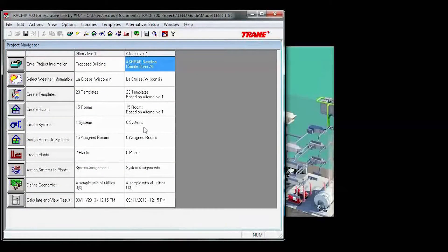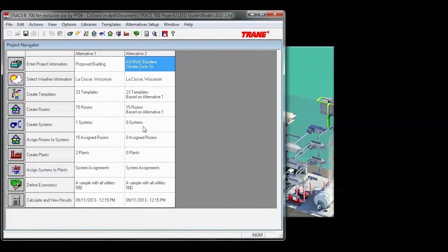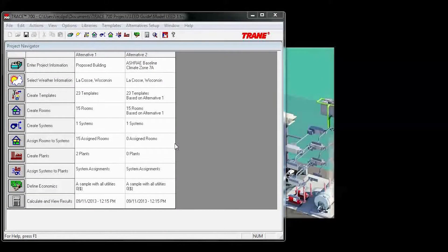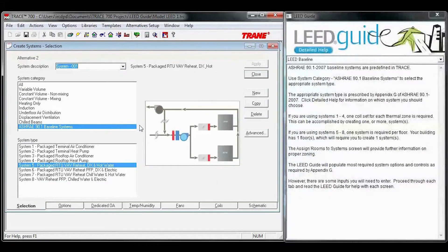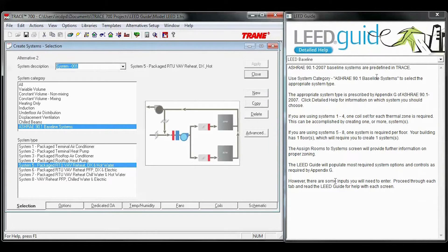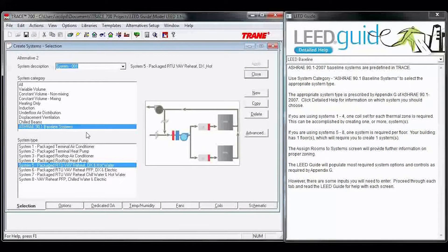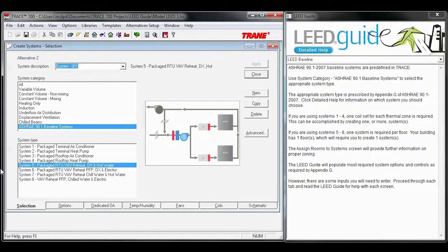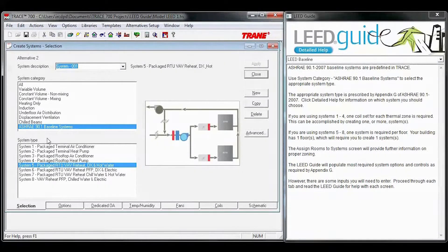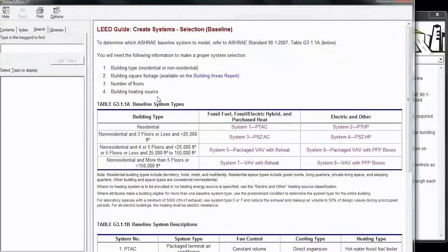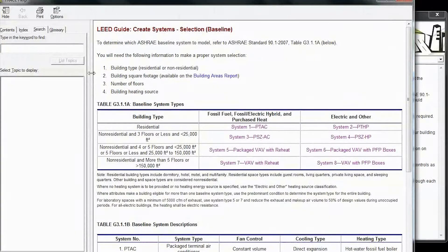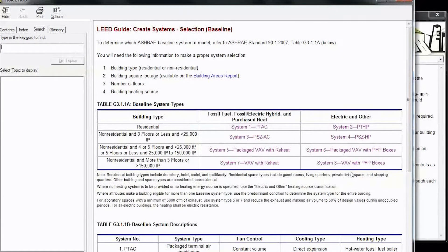Once you're satisfied with your baseline building, you can move on to systems. Once you've completed your baseline building, you can move on to create systems. When you open create systems, you'll see the LEED guide on the right, new system category, ASHRAE 90.1 baseline systems, and then the eight baseline systems. If you don't know which system type you need to model, you can click on detailed help. Four factors here will put you into one of the eight baseline systems.